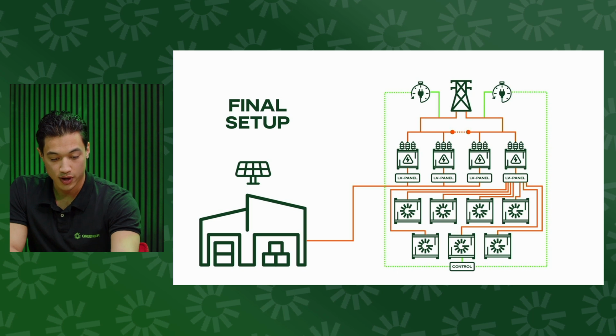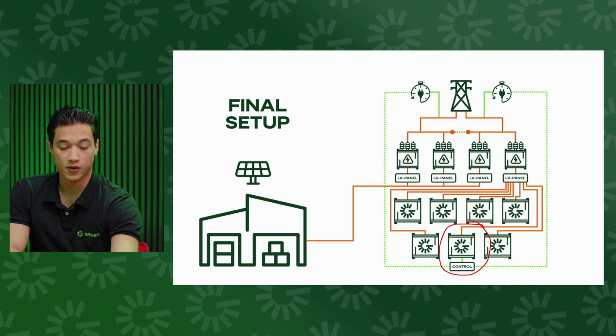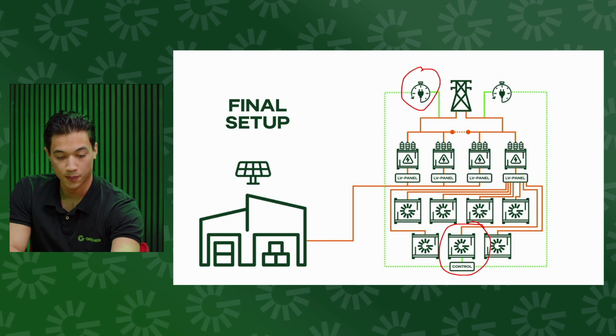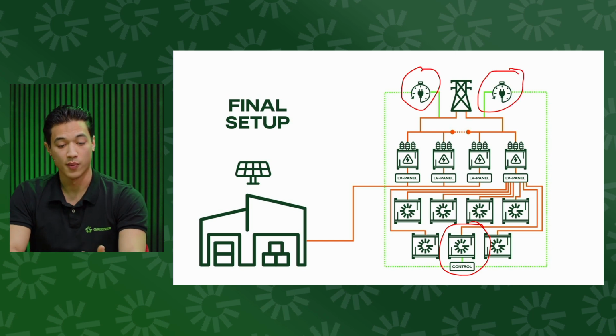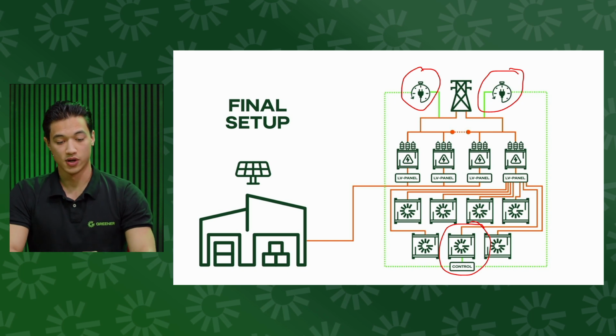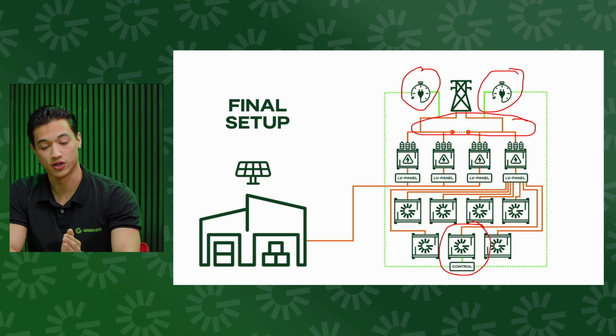That controlling battery is communicating with the energy meters on top here. It's gathering all the data coming from this energy meter and decides based on that data what the cluster needs to do. So if they measure 3 megawatts, which is the maximum capacity they can use from the grid, and there's more power than that, then the batteries, all the clusters, will provide additional power. If there's less than 3 megawatts being used, then the batteries can charge.